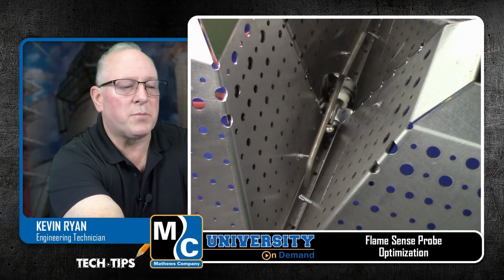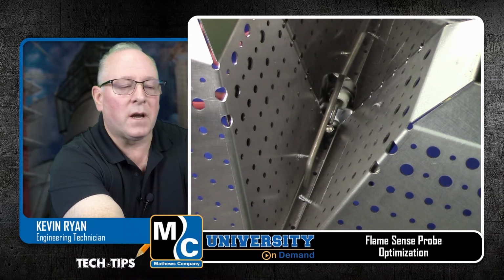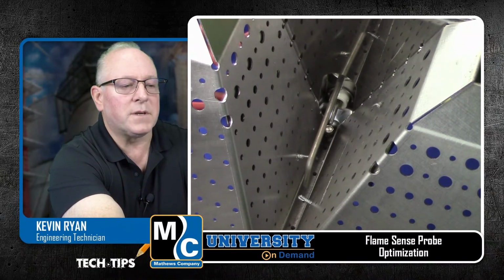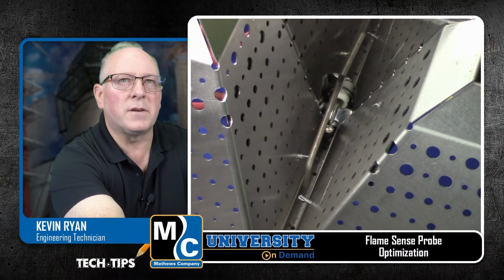You can move this probe, and coincidentally there are Phillips screws on a collar just outside the burner here that I'm loosening up as I'm doing this. You can loosen these up and they'll slide in and out and turn. That's what I'm doing with the flame sense probe too, so you can see the igniter piece is actually moving back and forth.